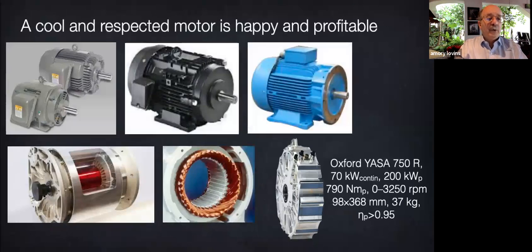Now, motor efficiency also depends on proper power supply, clean, calibrated, balanced, on precise laser shaft alignment, on avoidance of overhung load, sideways pulls on the shaft that can cut the bearing life at least 5 to 10-fold, especially with, say, fans that are driven by a V-belt that keeps pulling on the shaft. Motor efficiency depends on a white lab coat lubrication culture that dispenses a precise dose of special ultra clean, up-to-date medicine to the bearings, which have Swiss watch-like micro-inch tolerances.